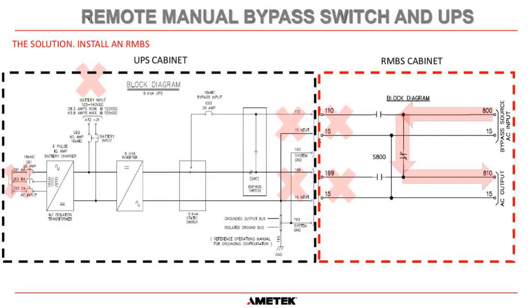So this is what the drawing looks like if you install an RMBS. Obviously, what I've done here is I've combined two drawings. We have an older type UPS that has an internal bypass switch here, and we have added an RMBS cabinet, which is external to the UPS. Okay, usually mounted on a wall somewhere in the same room.